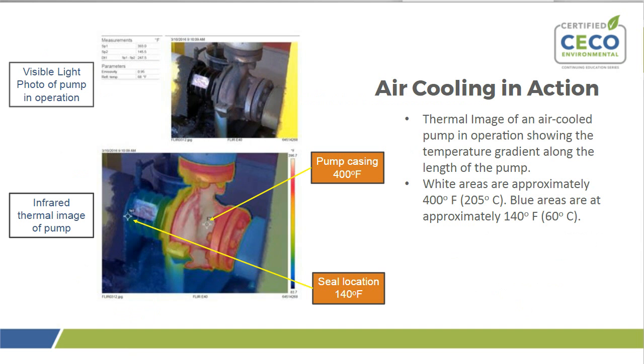So in this case, you can see an air-cooled pump. The top picture is basically the pump operating in visible light. The pump is spinning away, doing its thing. And then we took that same pump and took an infrared thermal image of the pump itself, and that's located in the lower photograph there. And you can see the white areas are actually 400 degrees F.